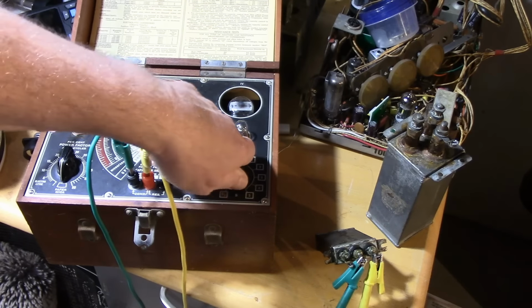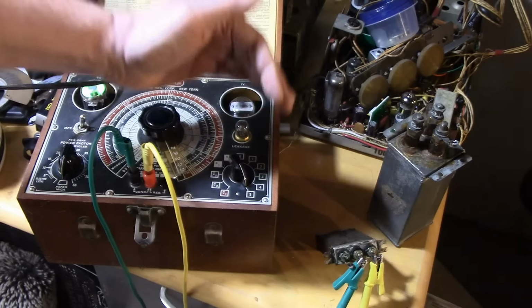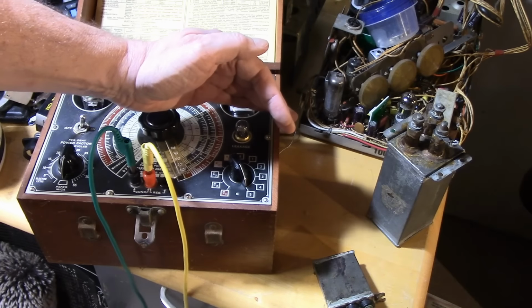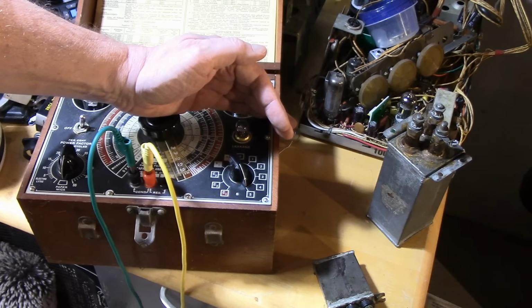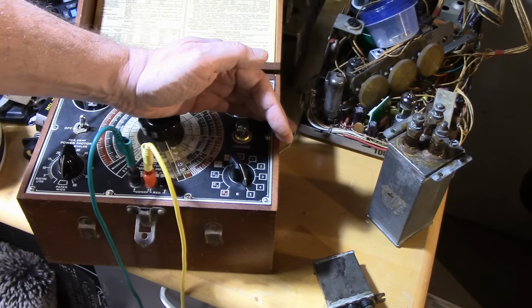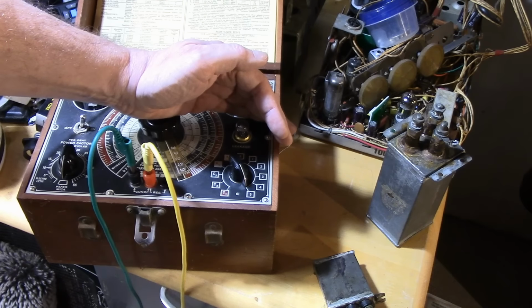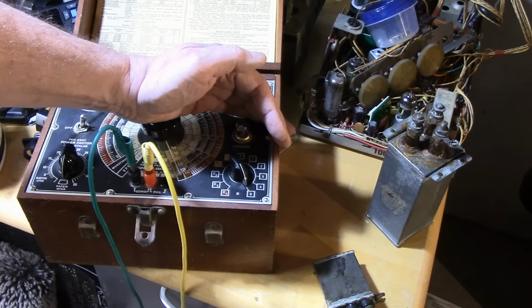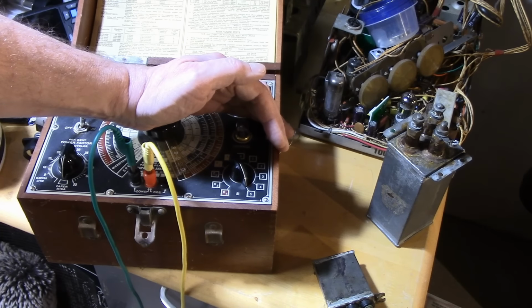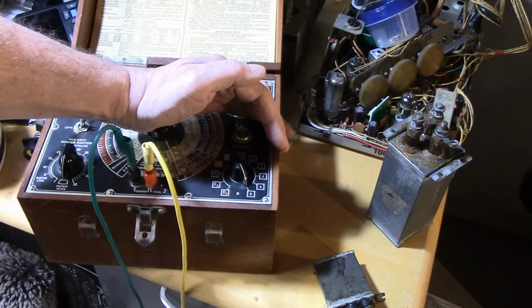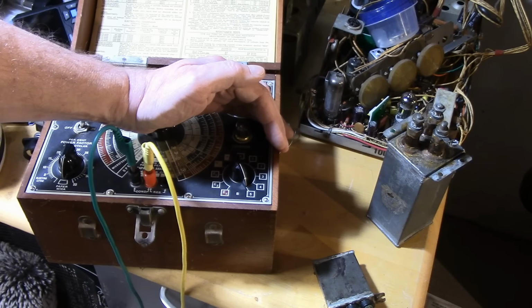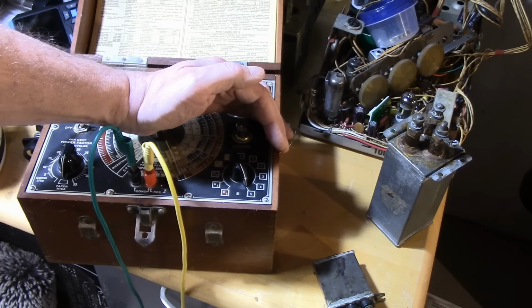So again, let's check for leakage first. Ooh - so at about 500 volts, that is occasionally flickering. That light should never come on. How fast it flashes indicates how leaky it is, so I can't give you a microamps reading, but the fact that it came on at all, that's not good.